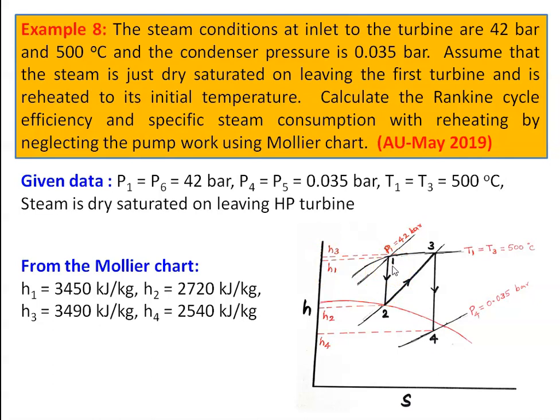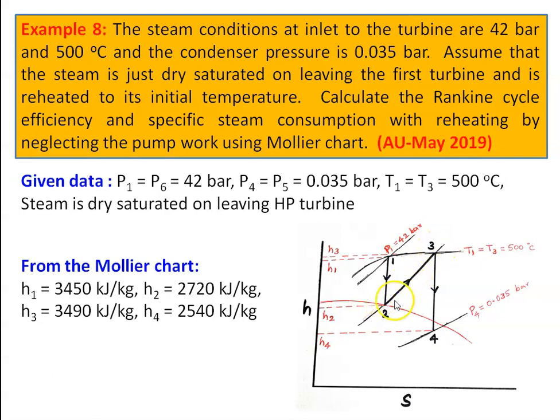For constant entropy, draw a vertical line. The condition is the steam is dry saturated on leaving the HP turbine, so draw the vertical line and stop on the saturation line — this is point 2. The enthalpy H2 = 2720 kJ/kg. Along the pressure line, move to where it intersects at 500°C — this is point 3, and H3 = 3490 kJ/kg. From point 3, the steam expands in the low pressure turbine — draw a vertical line to meet the condenser pressure P4 = 0.035 bar, which is below the saturation line. H4 = 2540 kJ/kg.